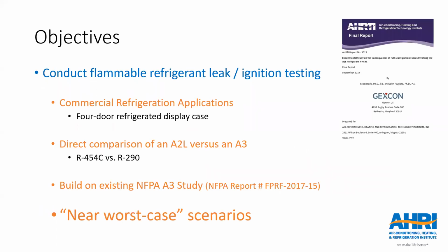So today we're going to talk about the results of the AHRI 9013 study, which was completed last year. This study performed flammable refrigerant leak and ignition testing with a focus on commercial refrigeration applications. For the scenarios we tested, we used a four-door refrigerated display case to simulate leaks and ignitions.